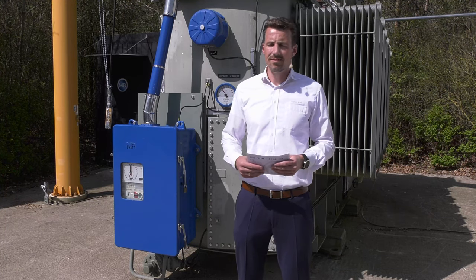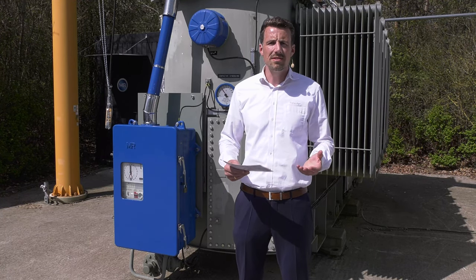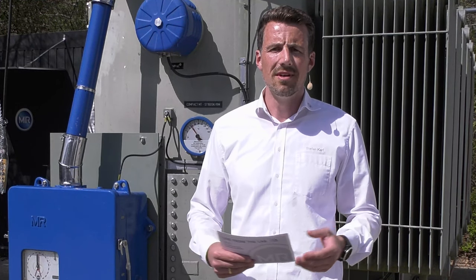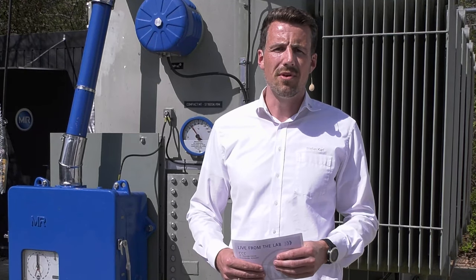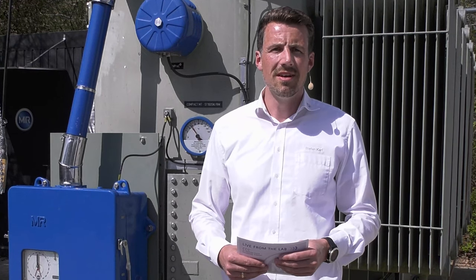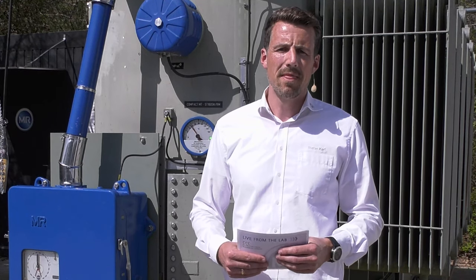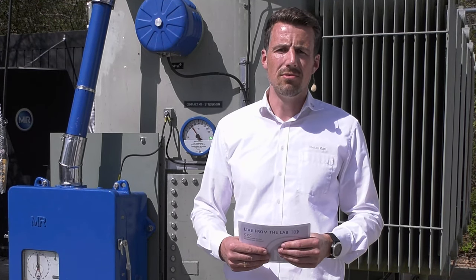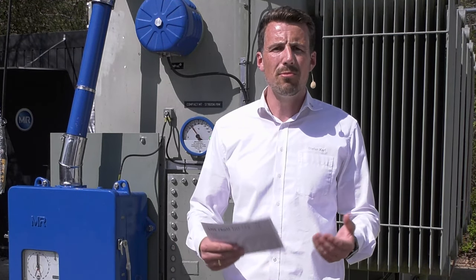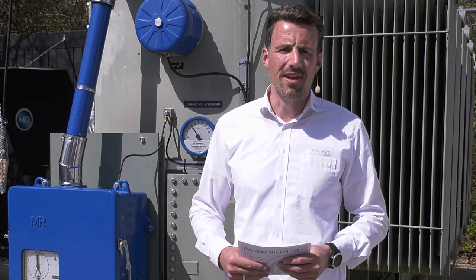So a replacement of a motor drive unit during the lifetime of a power transformer is very likely and can have different reasons. For example, modernization during a midlife refurbishment, retrofitting with new functions such as automatic voltage regulation, monitoring devices, and so on. Failure prevention due to regular errors of the old one, or even digitalization and communication can be the requirement of a grid operator today.